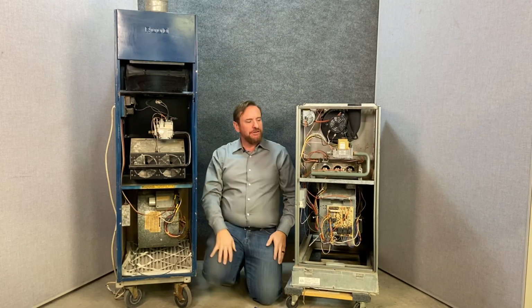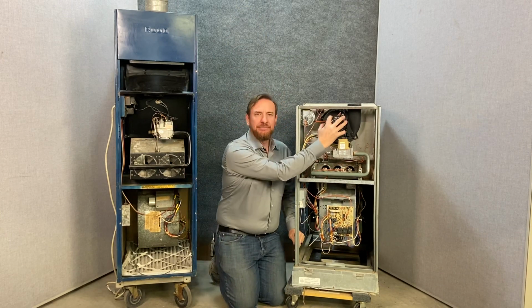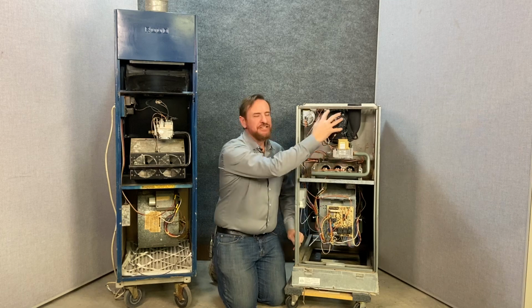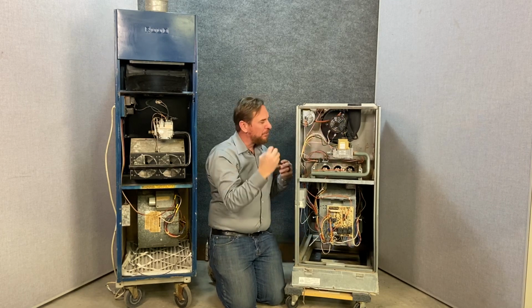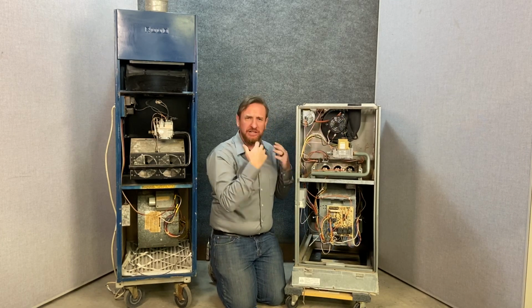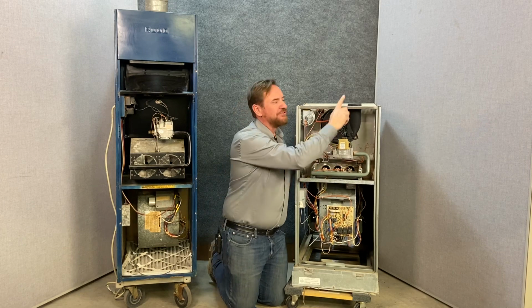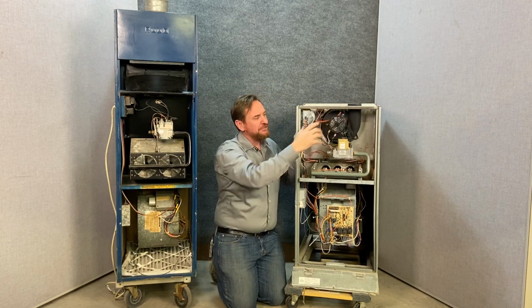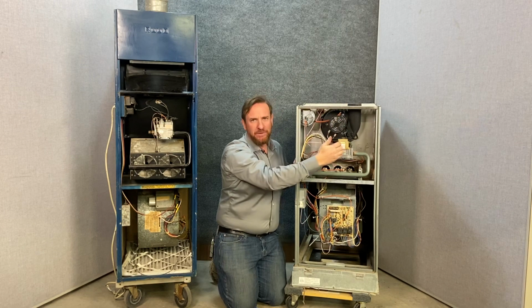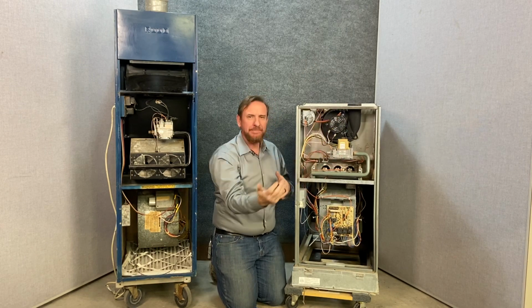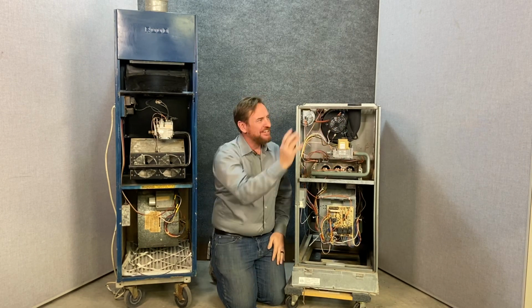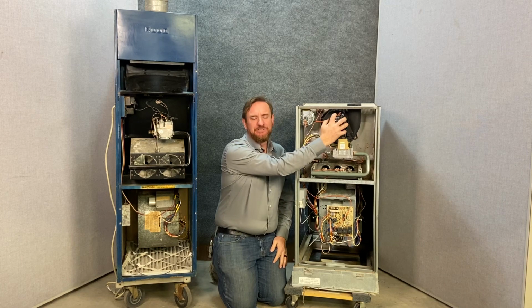With the new furnaces, what we have is this inducer fan motor. This control board energizes this fan motor first, and it pulls a draft through the heat exchanger, so it clears out the heat exchanger as well as starts the draft to the flue pipe. So this way, if you have a windy day and it's pushing air back down, it's not going to be dumping those combustion gases out into this closet. So this motor right there makes it more efficient.